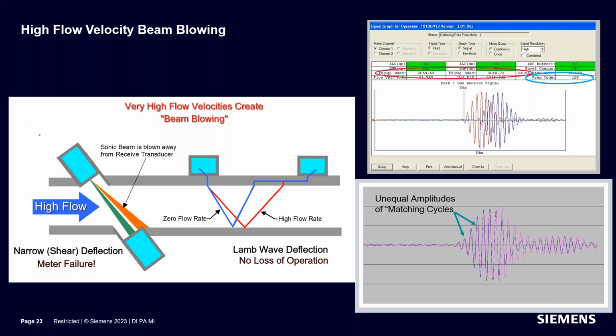And so correlation is how we can tell how many cycles of phase shift are occurring. With them sitting right on top of each other, now we can see the difference between the two waveforms. You can see that the red one, which is the one that's traveling downstream and arriving faster, has higher amplitude on the back end, whereas the blue one has higher amplitude on the front end. And there's a differential.